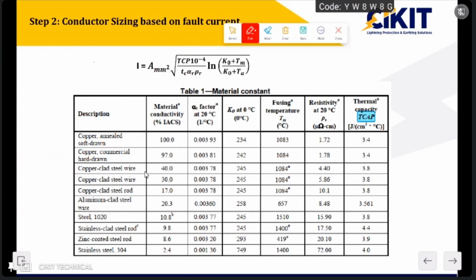The standard has provided the different parameter values involved in this calculation, for different materials. The materials provided are copper, stainless steel, aluminum, copper coated steel, zinc coated steel, and so on. Among these materials, nowadays we are mainly using copper coated steel for earthing applications, because of its performance and, at the same time, the cost is cheaper than copper. So nowadays we are mainly going for copper coated steel.